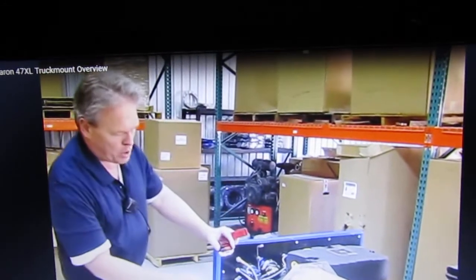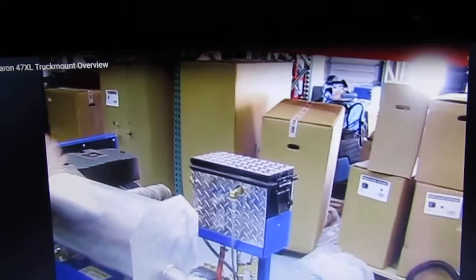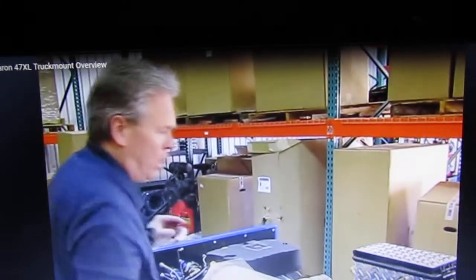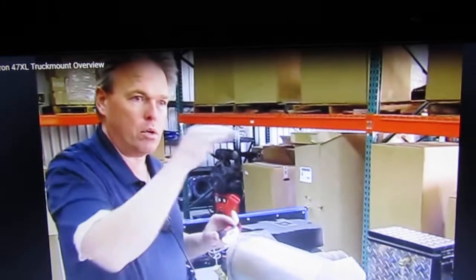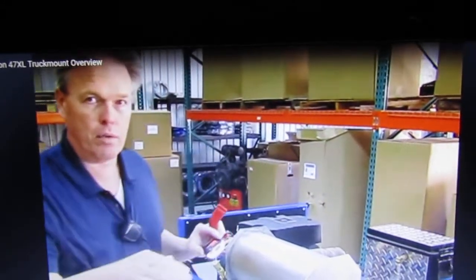So a small amount of that heat is automatically put back in this water box. And so that water box is kind of being used like a preheater, but it's also tapering the temperature of the system. To keep it from getting too hot, you see right here, there's actually a 145-degree sensor. This is actually monitoring the temperature of the box, and when this gets too hot, it's going to open up and it's going to let water suck back to your waste tank down through one of these hoses again.